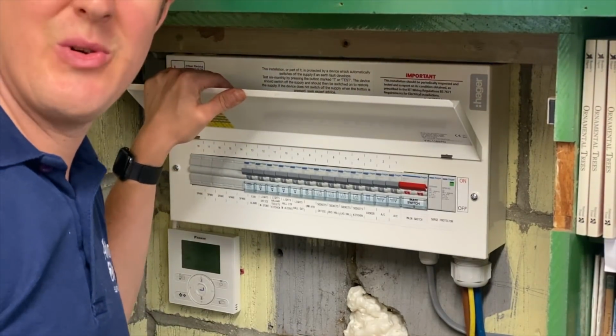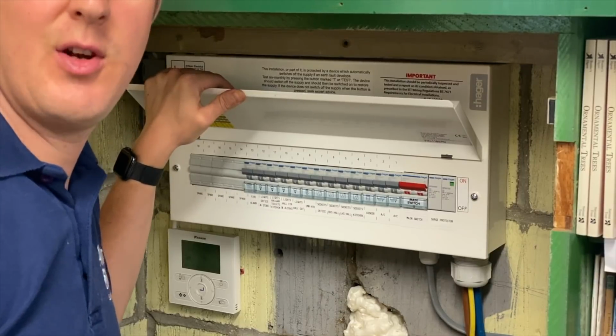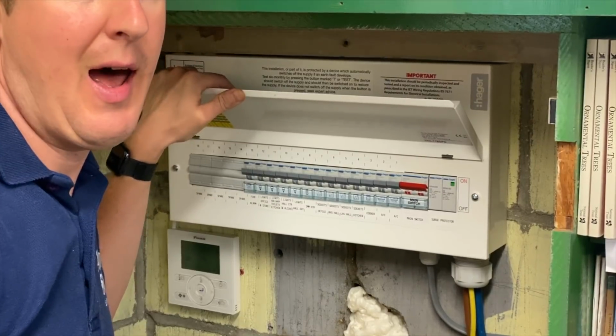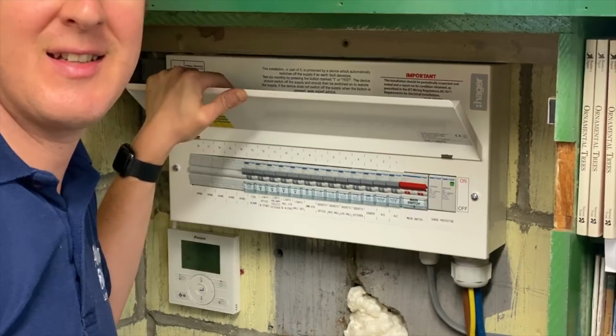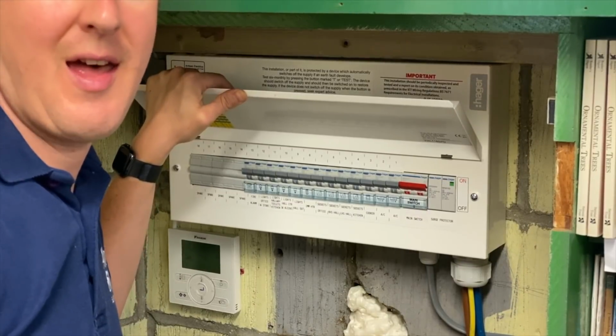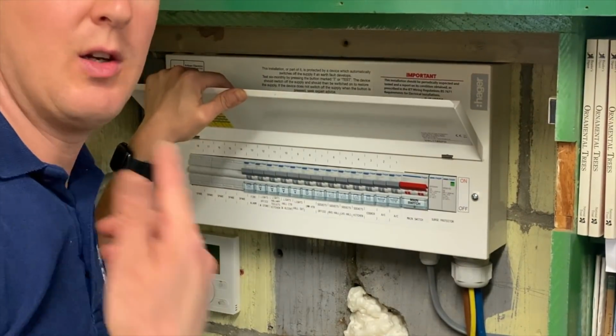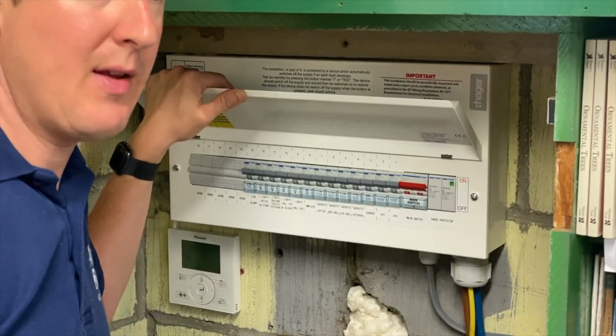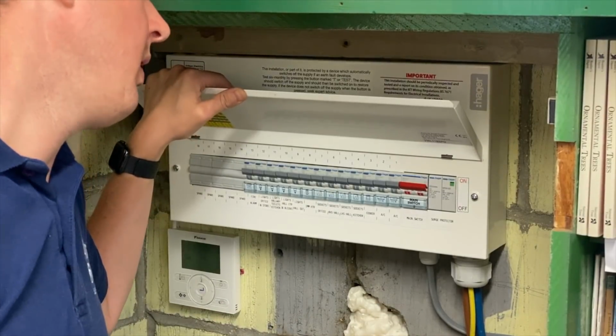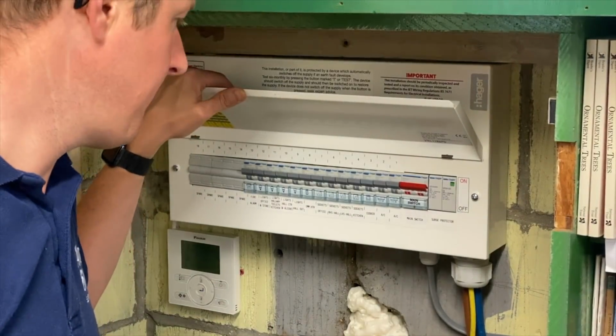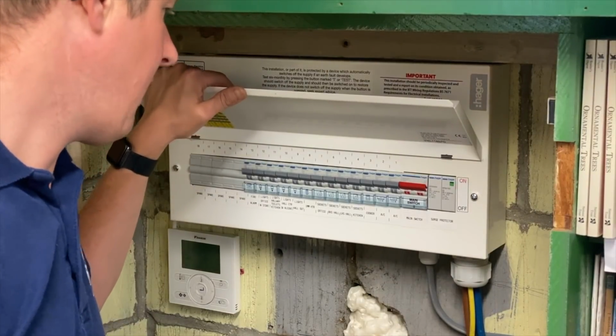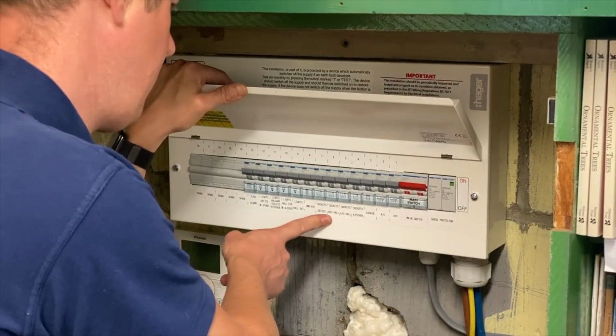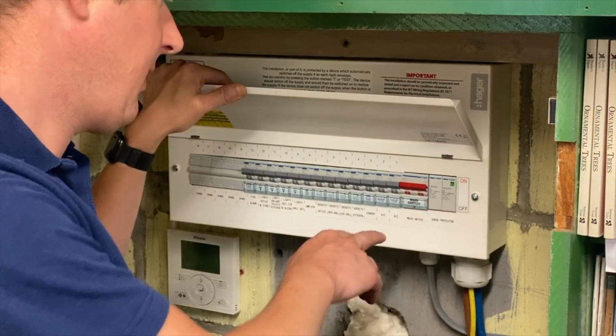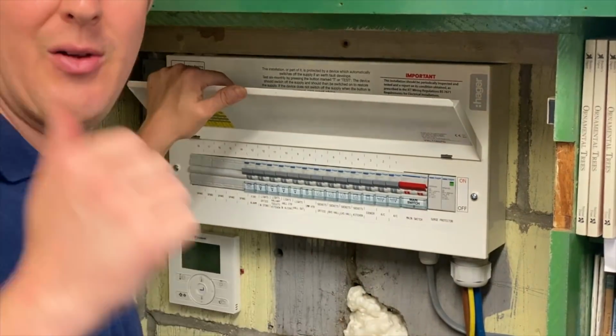So now our final set of tests are our earth loop impedance tests, which are done at the furthest point on each circuit. We take a resistance reading there to make sure that the earth loop impedance at that point is not too high, so that the circuit breaker will still trip in the event of a fault. We will start at the front and work our way through all the circuits until the end. So I'm going to start at the AC units outside.